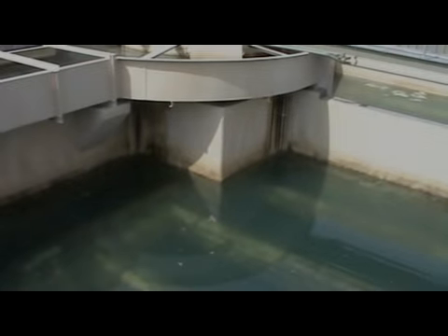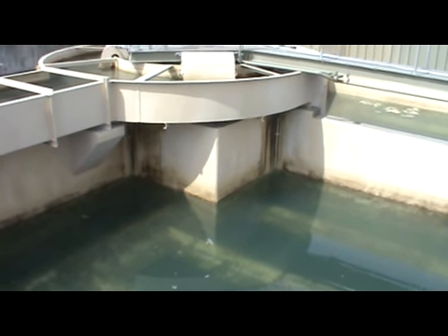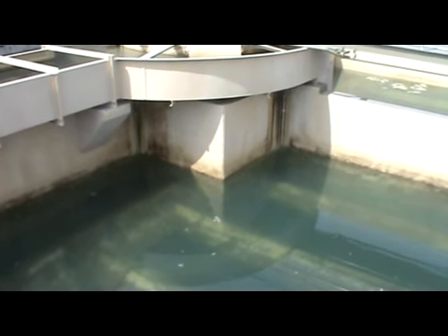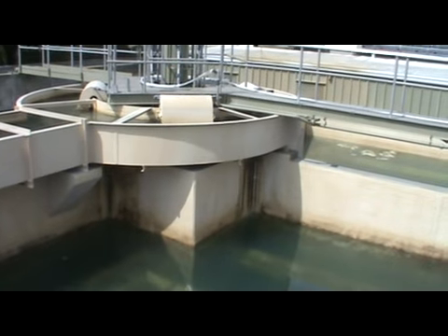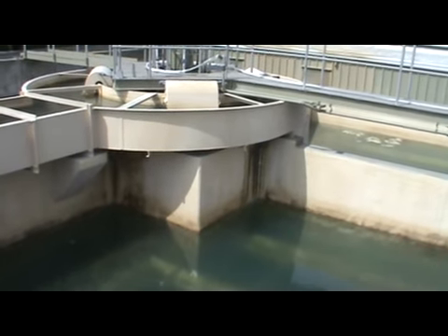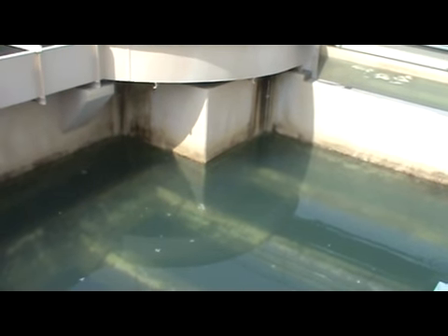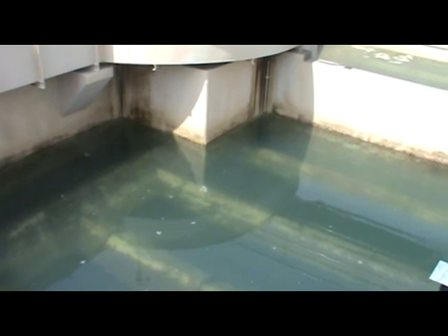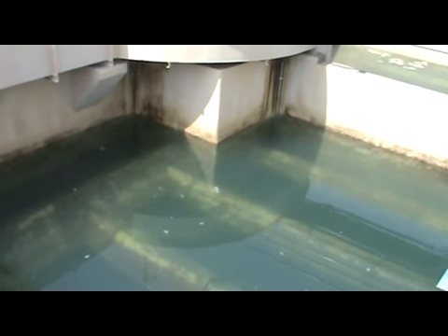When we backwash a filter bed, basically what happens is, first off, the inlet to the filter bed is closed. The effluent side of the filter bed is closed. I should say by inlet, meaning that connection is broken so water's not flowing into it. The effluent valve is closed and you go through what's called a drain period, where you drain down the water. The water drains to a washwater collection tank.